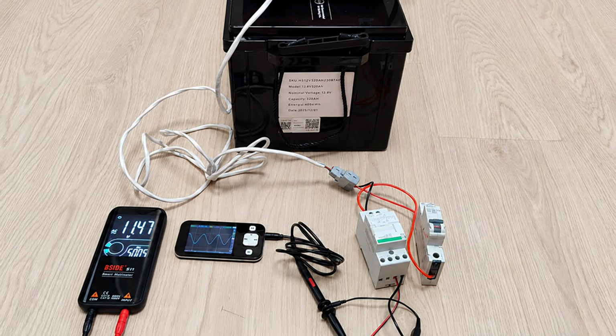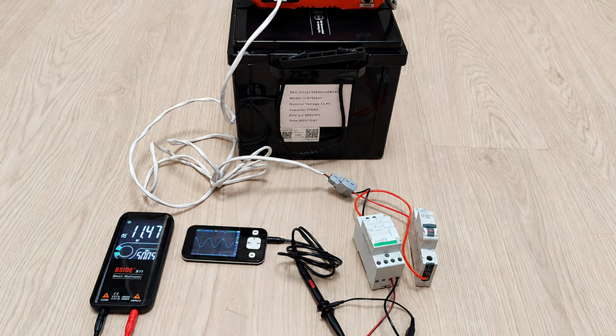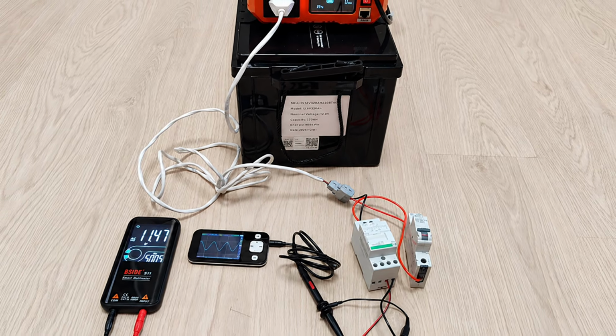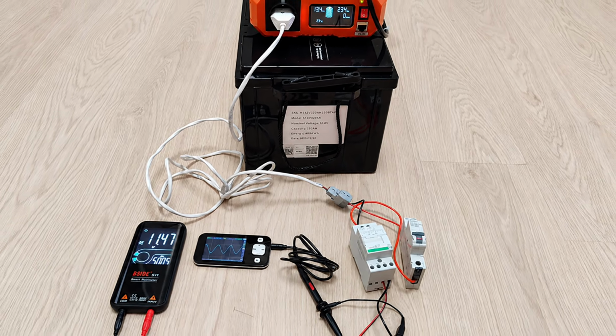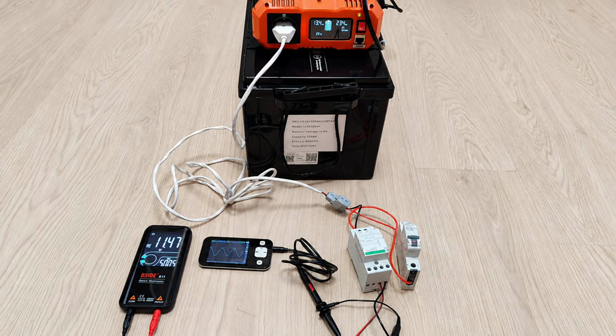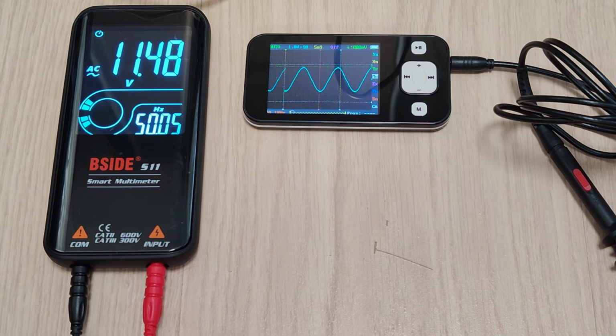Now I connect this same test bench to the inverter output. I make the first measurement without any additional load. In fact, the inverter is now operating almost at idle. I do not see any differences from the measurements on the city grid. The sine wave has the correct shape, the mains frequency is 50 Hz. Everything is fine.